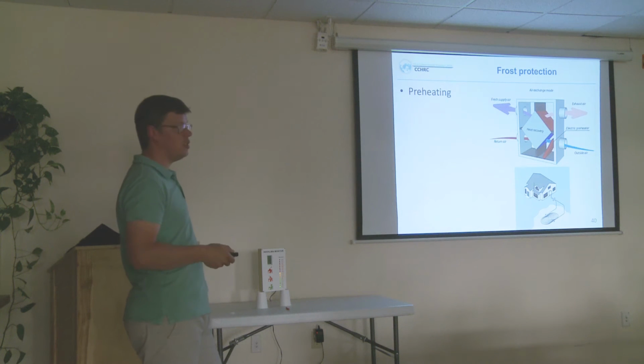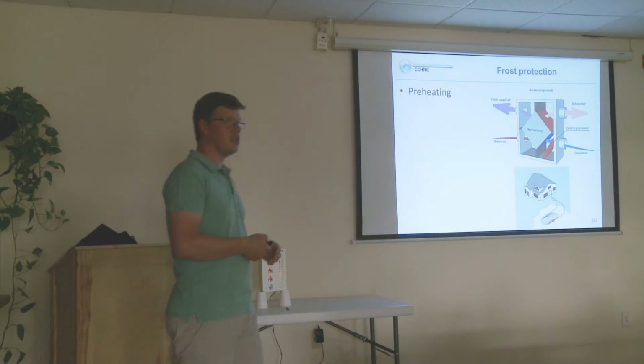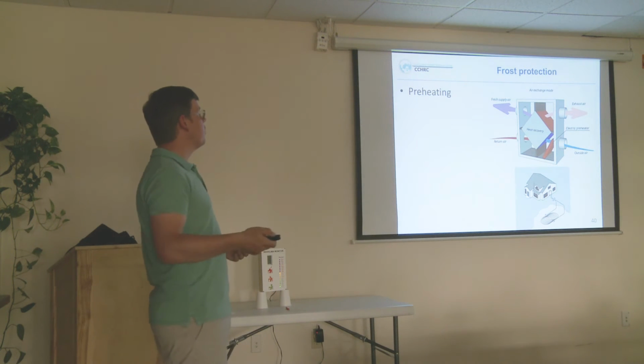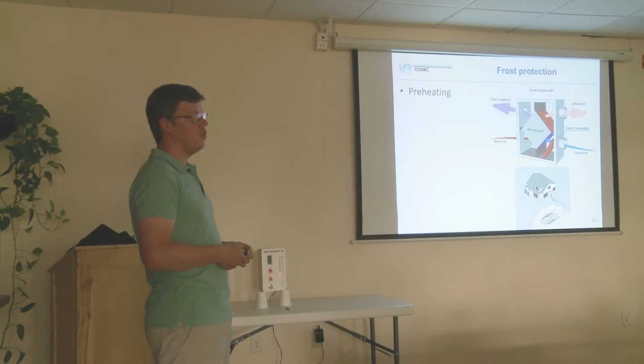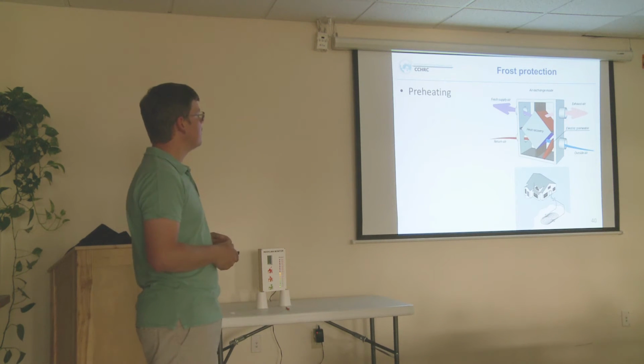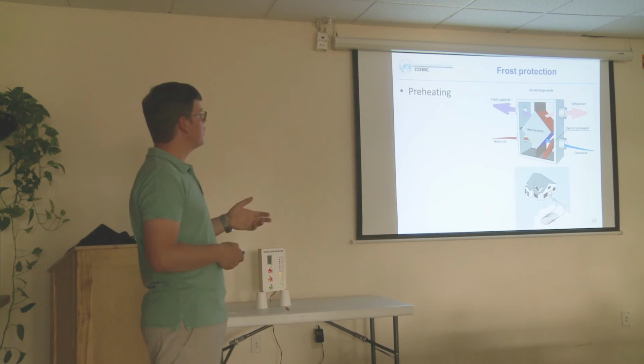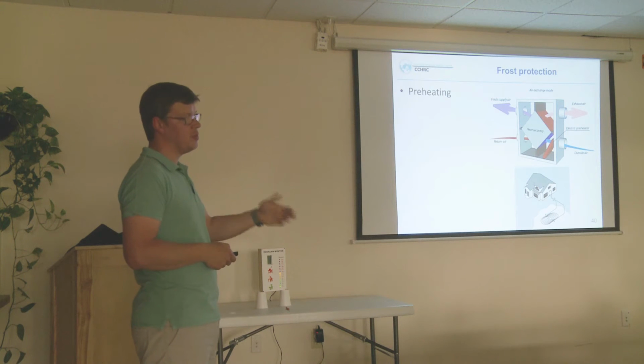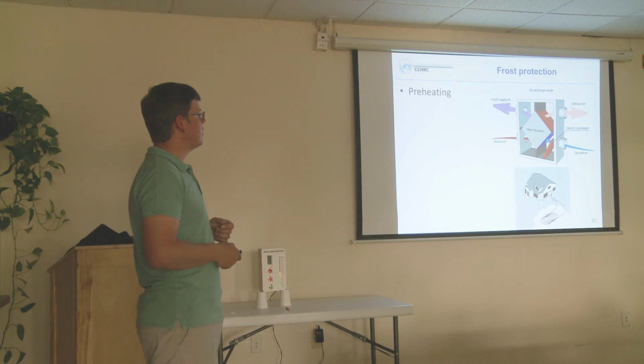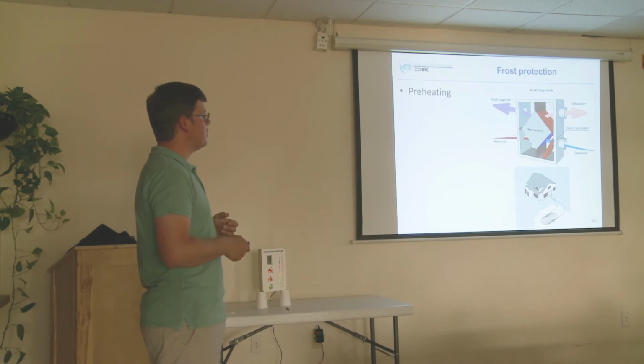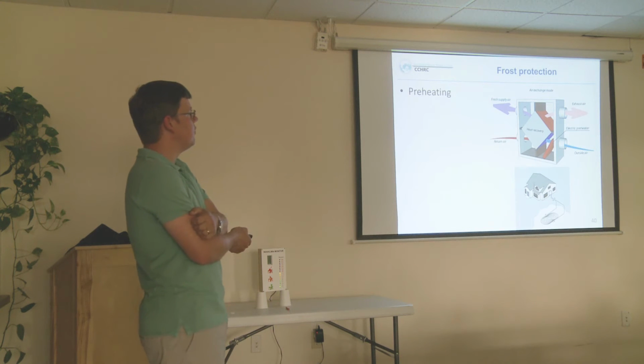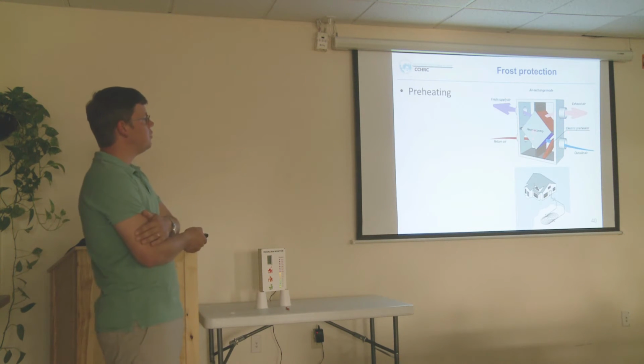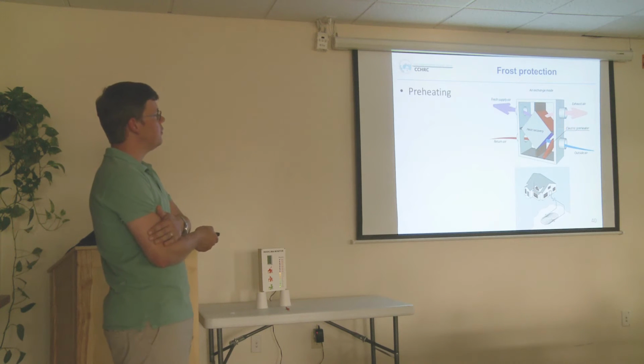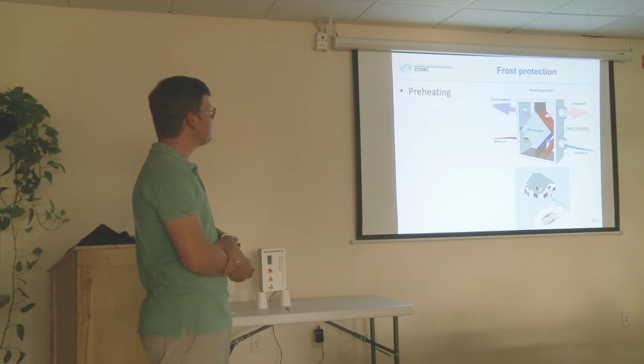There are several strategies which are used in the ventilation units nowadays. The most simple one, and probably the least effective one, is preheating. We can just have a simple electric element on the cold stream and have a controller set that if the outside temperature drops below something, just turn that electric element on and preheat the air. It is efficient to protect the core from ice formation, but it also reduces the efficiency as the temperature difference is lower.